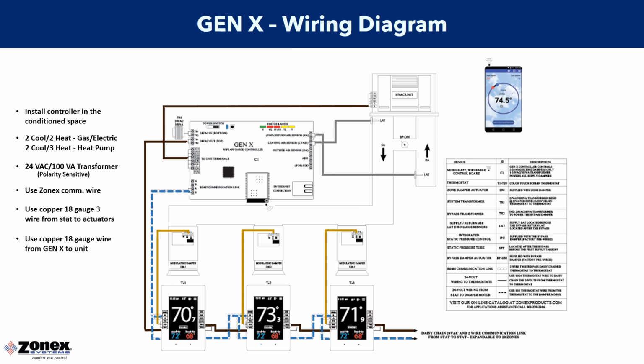On the bottom right-hand corner of the Zonex controller, you'll notice that there is an Ethernet connection for the controller. You want to make sure that a cable is run to allow for the controller to be plugged into their network. We recommend running a Cat5 shielded cable to help minimize any potential for noise being brought down on your network connection. The Zonex board is also equipped with a Wi-Fi chip. This chip is used for startup purposes and allows your device to connect directly to the board and commission it without any network present, so you can get your system up and running prior to having to wait for their network to be installed.